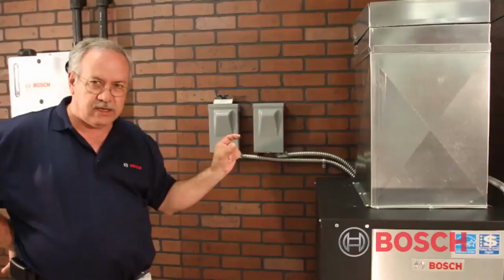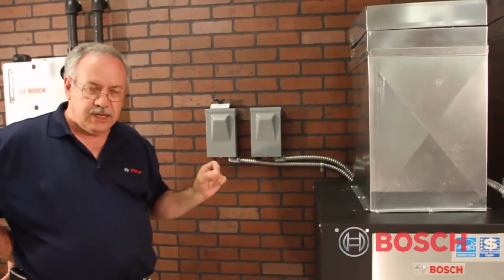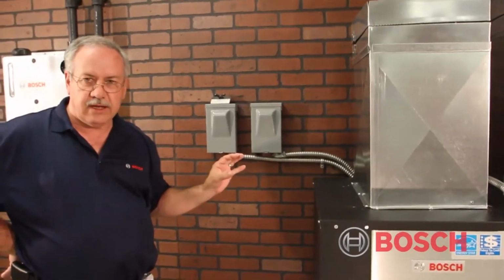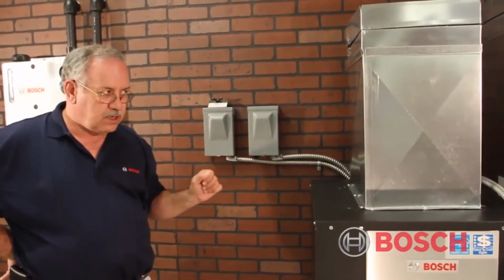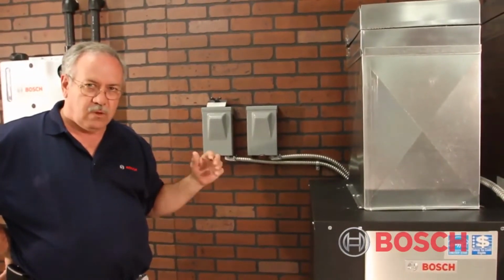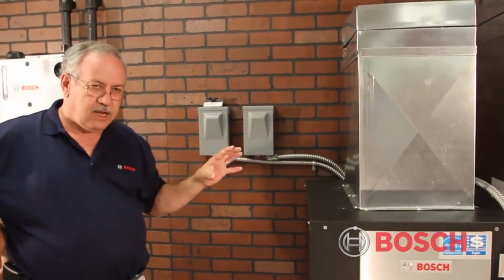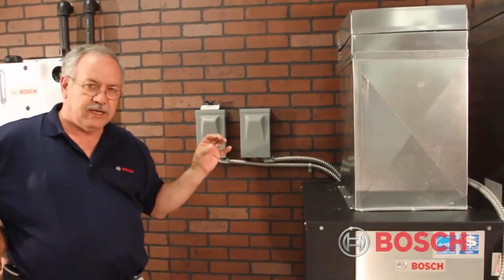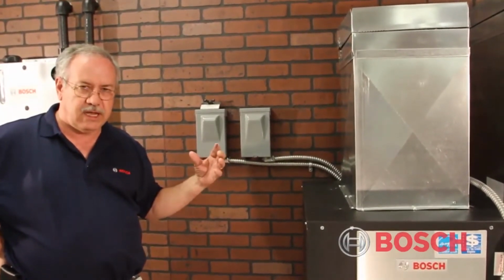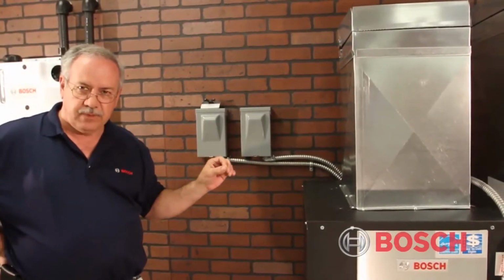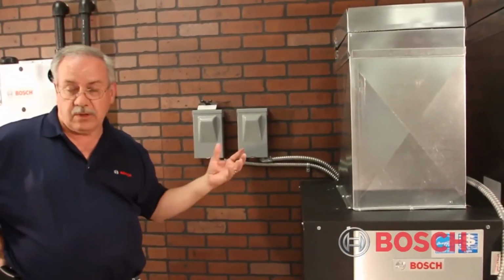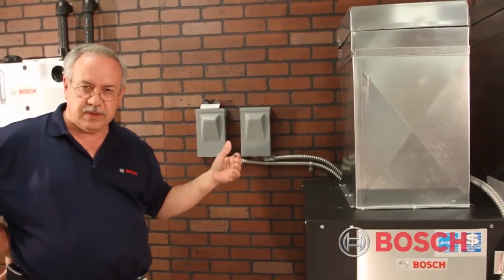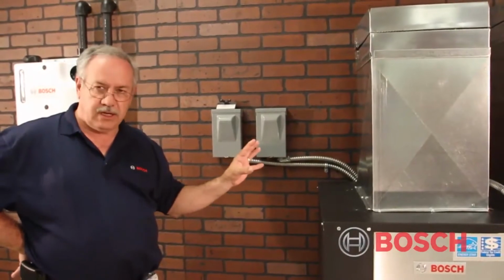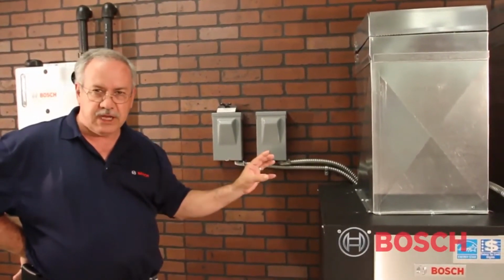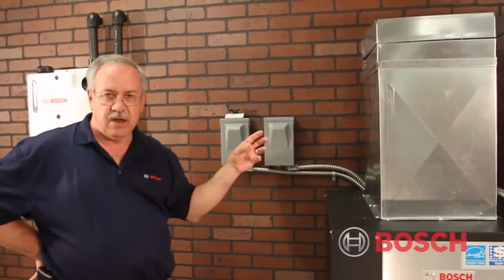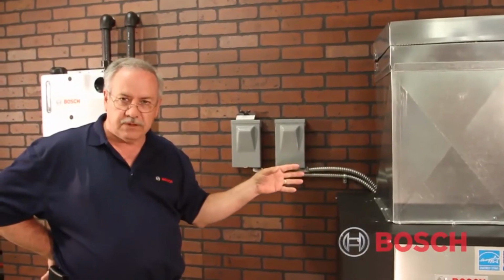When I get the biggest spread in delta T, or temperature rise, I'll plug in the numbers, then I can discontinue the test and calculate mathematically what the CFM is crossing this electric heater in the emergency heat mode. When we have heat pumps, typically the heating CFM with the heater energized is slightly more than what we would typically see as CFM per ton in the cooling cycle. Because in the cooling cycle we have moisture on the coil, and moisture creates friction, and thus we have less CFM being produced. But theoretically, heat pumps should blow about the same airflow in emergency heat mode as they will in typical first stage heating or second stage heating with a 2-stage compressor, or in first or second stage cooling.